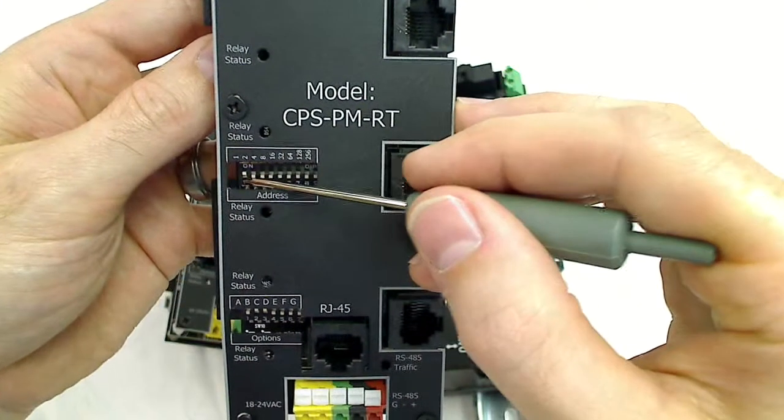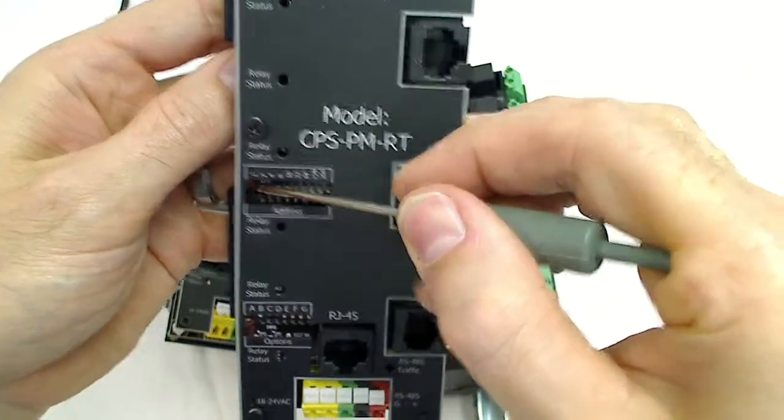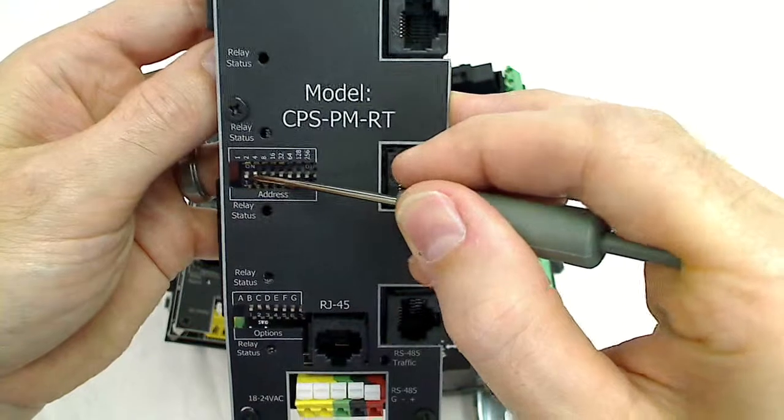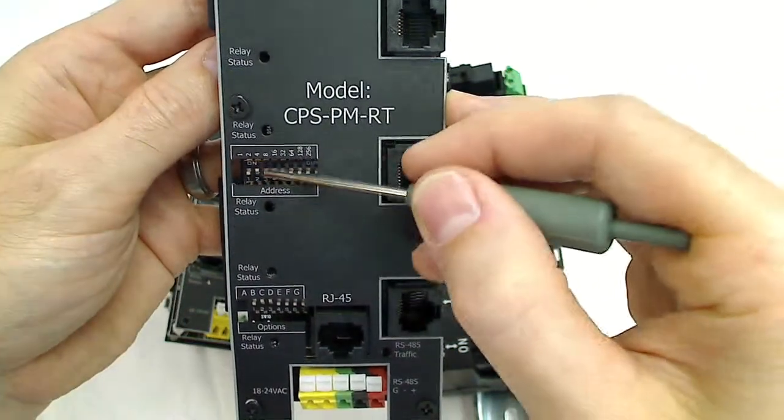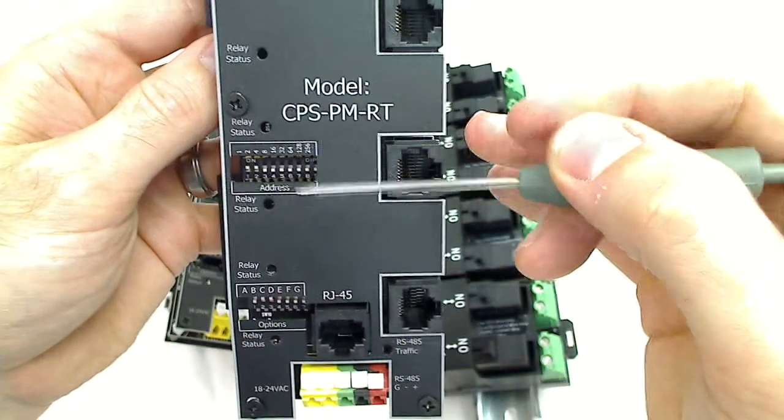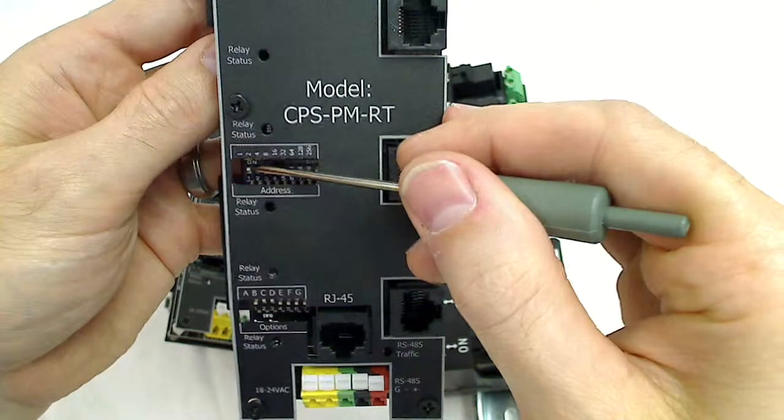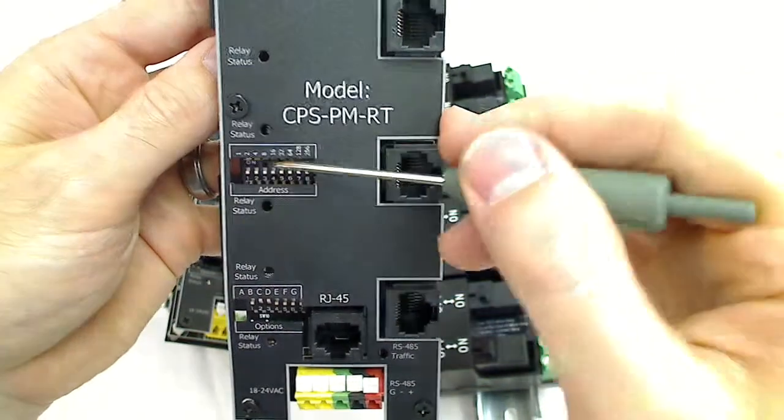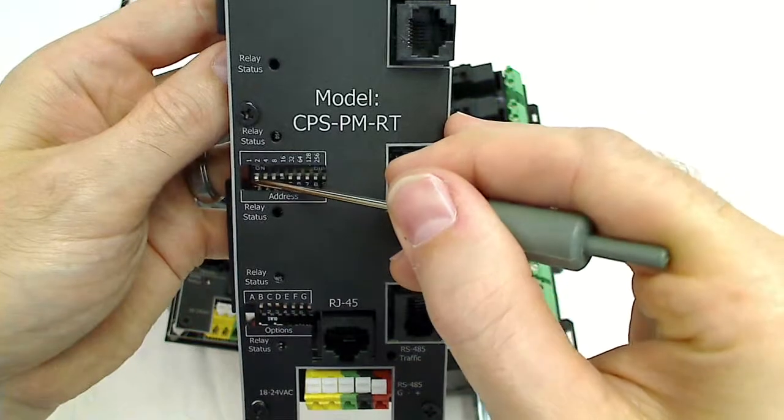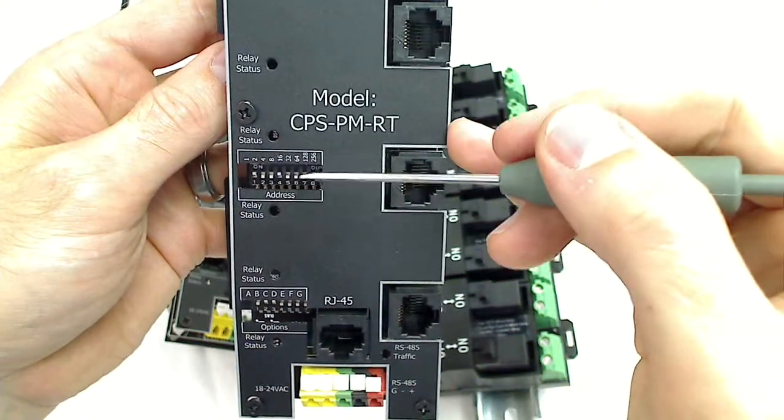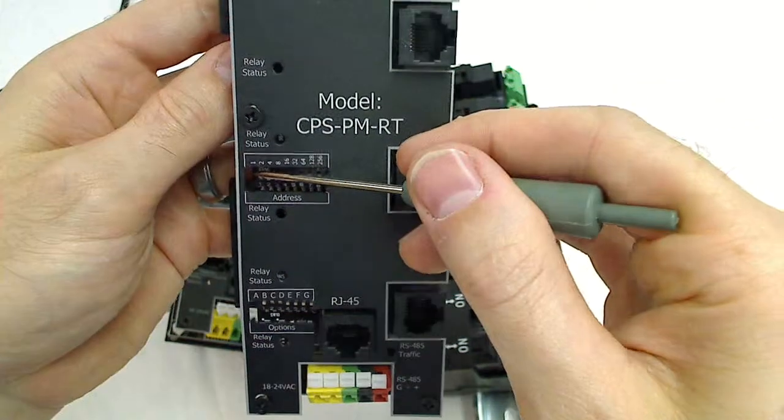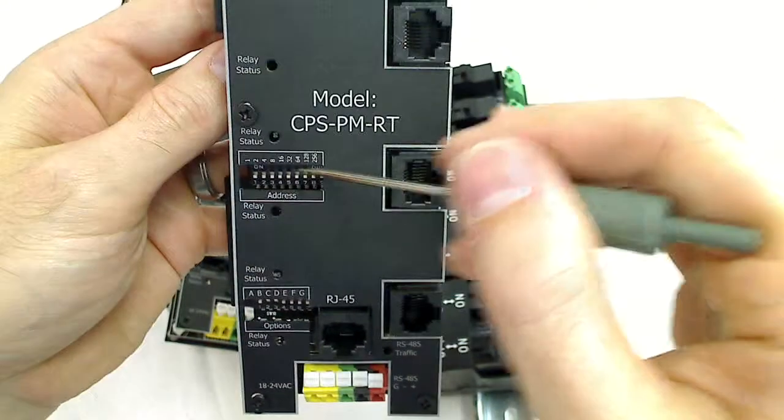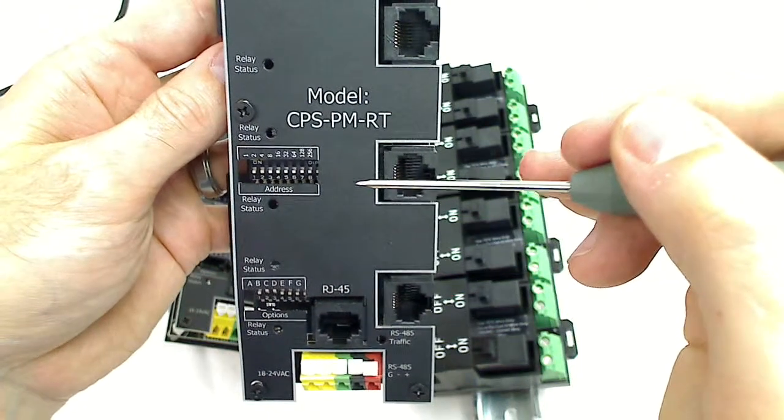So address one, you would turn on dip switch number one. For address two, you would turn on just dip switch number two. If you wanted address three, then you would turn on dip switches one and two. If you wanted address nine, you would turn on dip switches eight and one added together. Your address is a total of the values added up across your address dip switches.